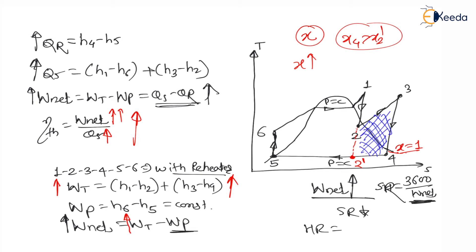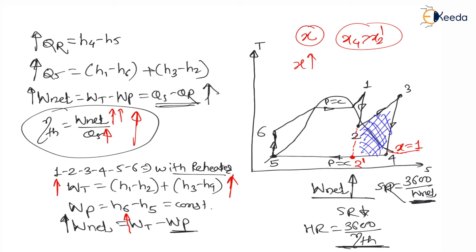Heat rate is 3600 / thermal efficiency. As thermal efficiency is increasing, heat rate is also decreasing. So in the case of reheat cycle, efficiency of the cycle is always increasing. In the Brayton cycle, we saw that because of reheat alone efficiency decreases — only reheat with regeneration increased efficiency for the Brayton cycle. But for the Rankine cycle, with reheat only, efficiency is increasing.